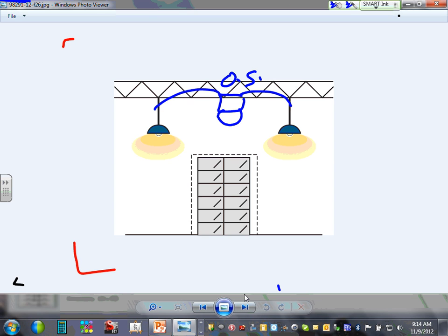They said if you have an electrical room and you have to have a light, the light has to be manually operated. So the only way I can wire this is to have a switch. Or the occupancy sensor has to have manual override. You can put them in the auto position or an on-off position. Manual override. Can I have thumbs up, Chad, for the light? Anybody knows why we need light around electrical equipment? Duh, we are working with energized equipment. You need to be able to see it, right?